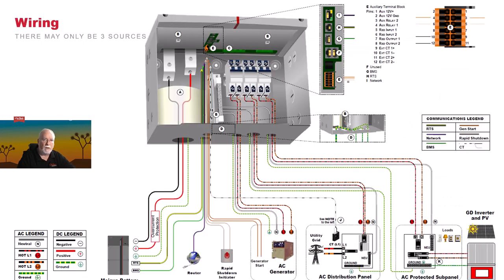So moving on from batteries, let's just take a quick look again at connections. So we do have the battery section down here with the positive, the negative, the ground, possibly a remote temperature probe or a BMS CAN interface. You'll have an Ethernet that'll be plugged into a router, or it could be wireless. The rapid shutdown we discussed. The generator we're going to discuss in a future slide. And then our coupling to the grid, effectively our line 1, line 2, neutral, and ground. You'll also have your CTs in this.